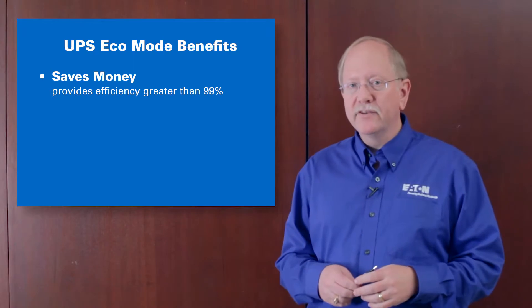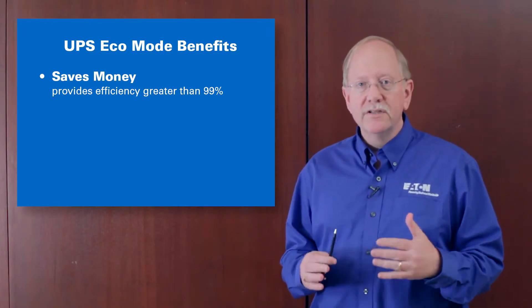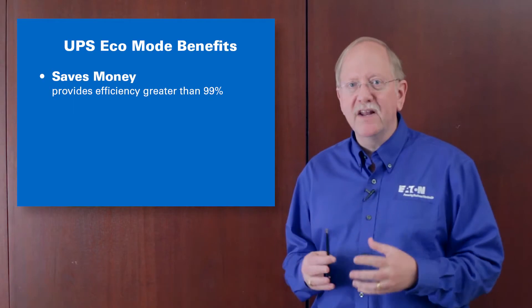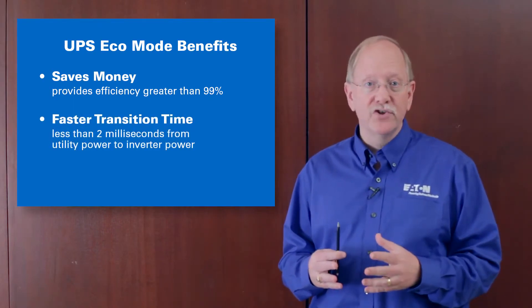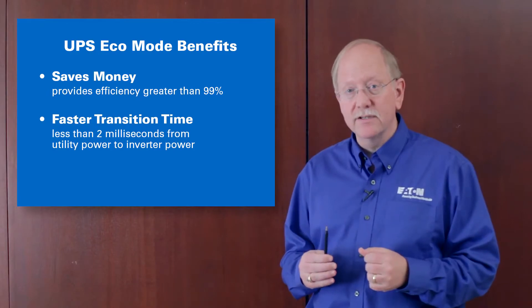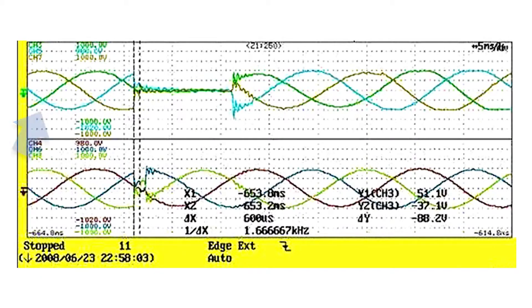By far the biggest concern with eco mode UPS operation is the observer has trouble accepting that we can in fact transition from static switch operation to double conversion operation in less than two milliseconds. So we use an oscilloscope trace as proof.